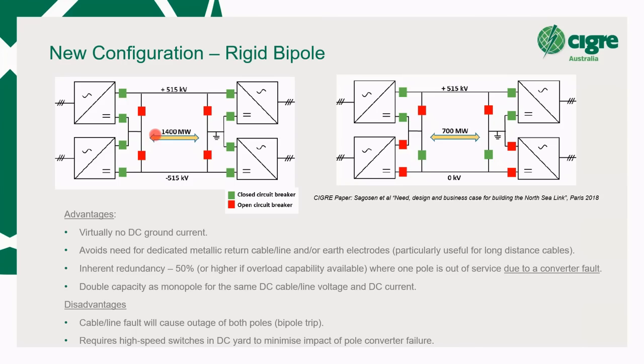And the idea here is if you get a fault in one of the converters, which is possibly more likely than a submarine cable fault, for example, the high speed switches on the DC side will very, very quickly bypass the faulty converter and allow the system to operate as a monopole at half capacity without having to put in either an earth electrode or a metallic return. So this leads to, basically, you save on one cable. And hence, that's why it's very popular with the very long distance converter projects like the examples I just mentioned, 700 kilometers plus.